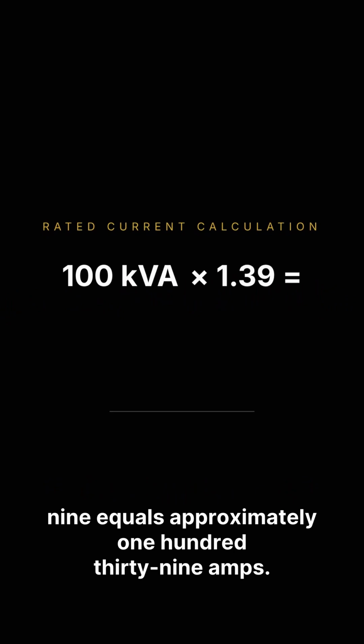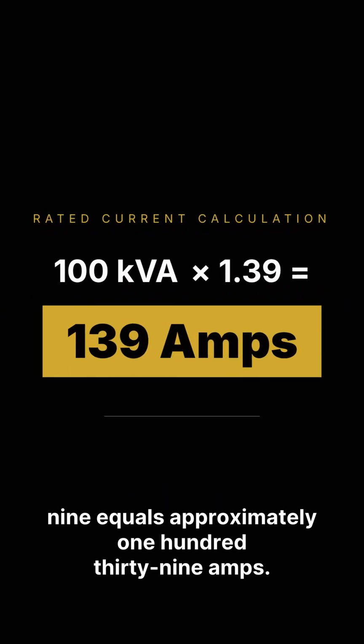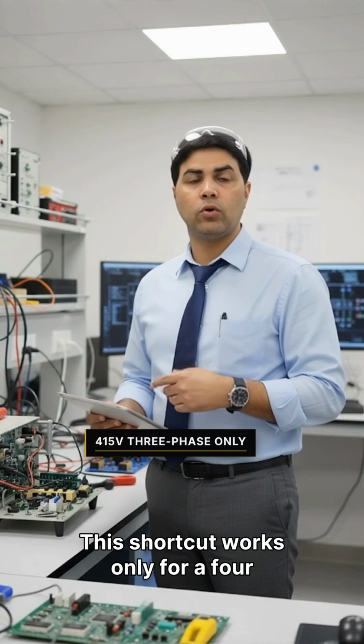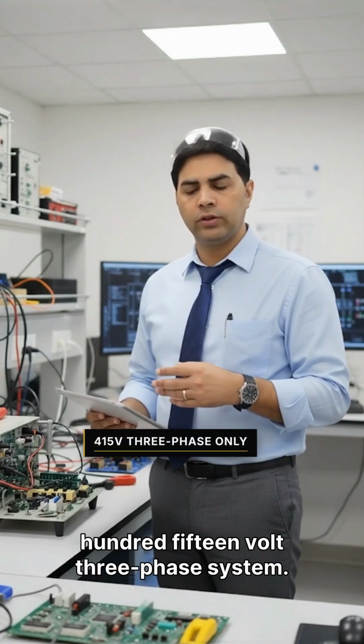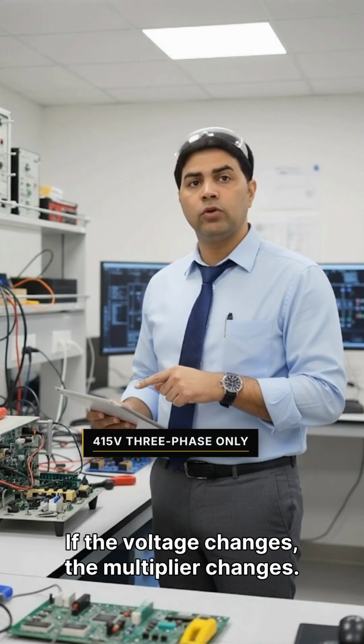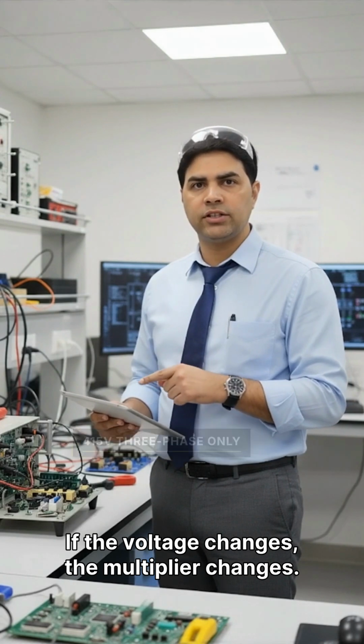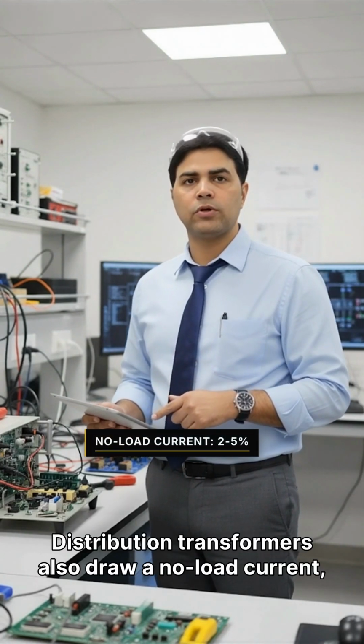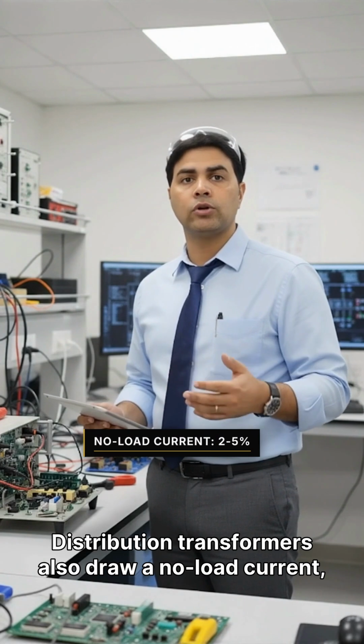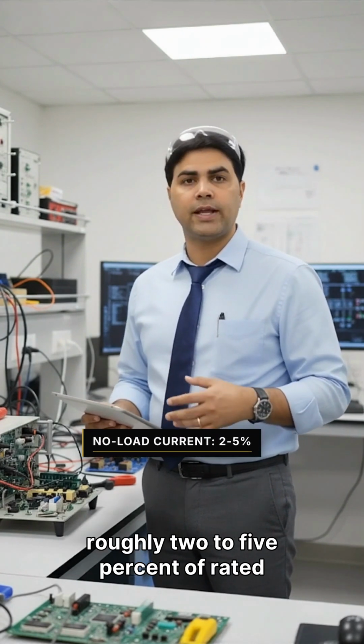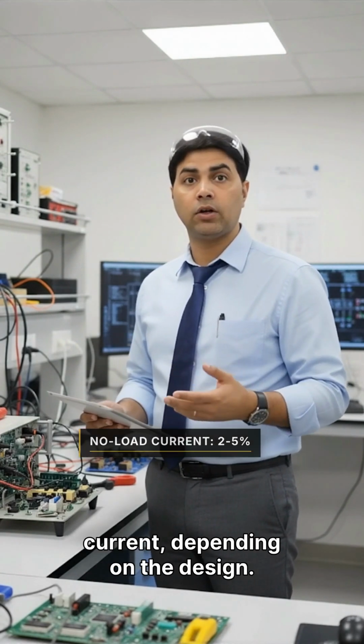100 multiplied by 1.39 equals approximately 139 amps. This shortcut works only for a 415 volt 3-phase system. If the voltage changes, the multiplier changes. Distribution transformers also draw a no-load current, roughly 2 to 5% of rated current depending on the design.